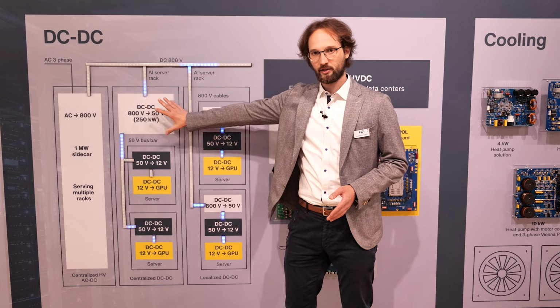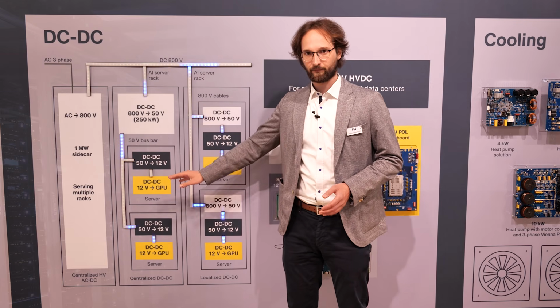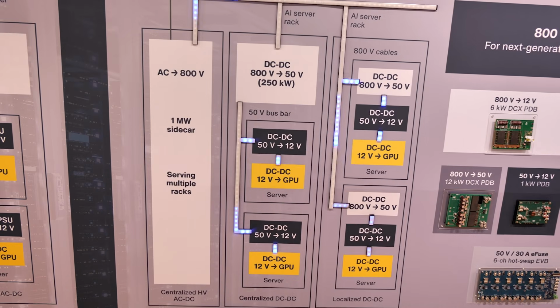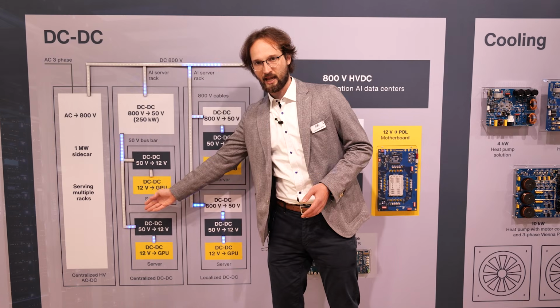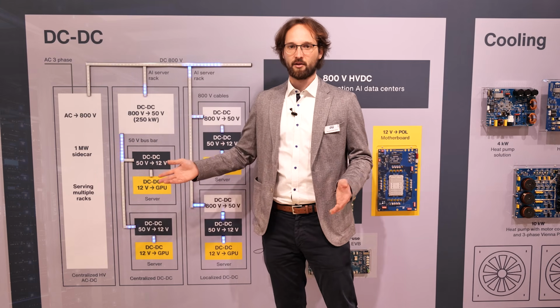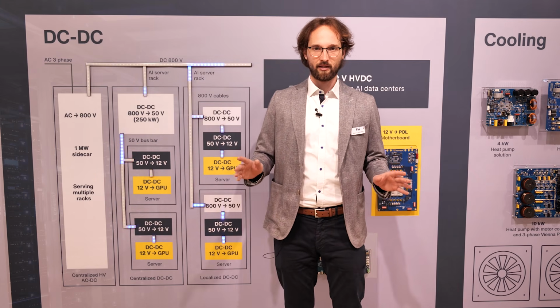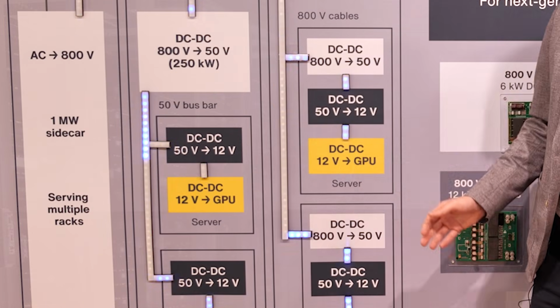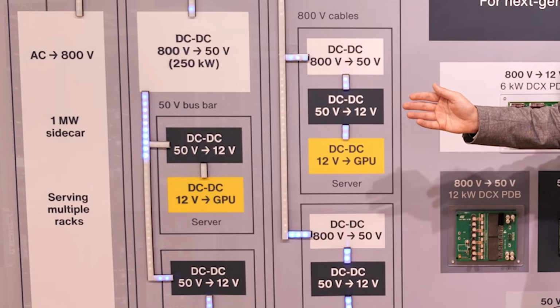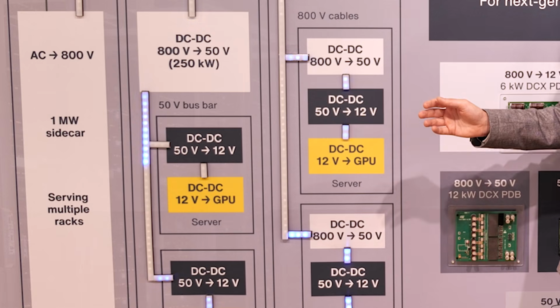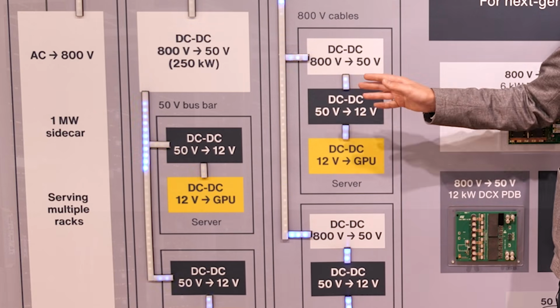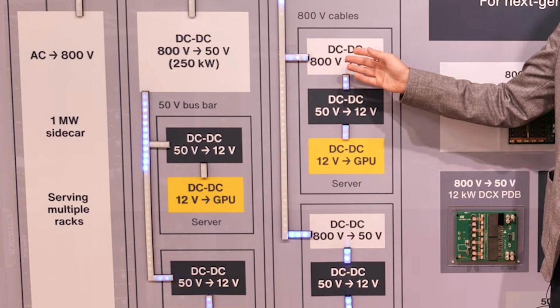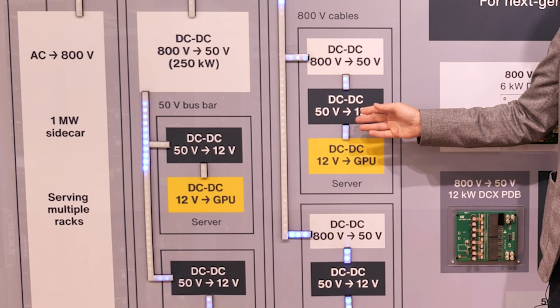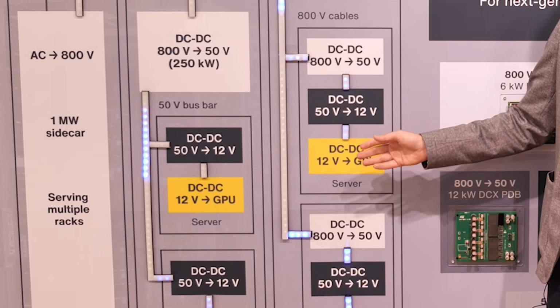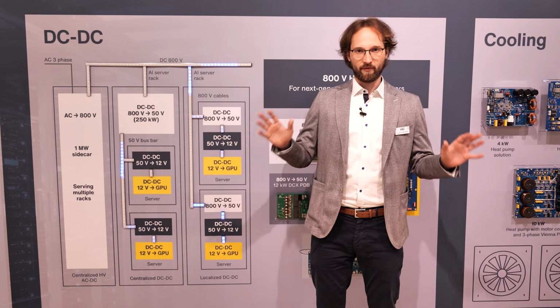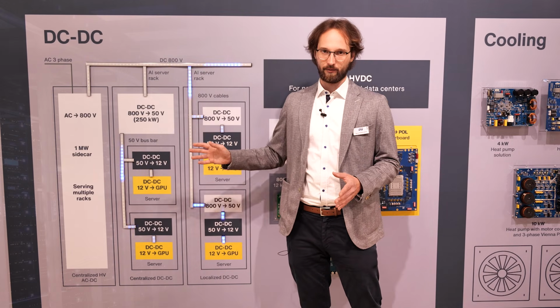The heavy lifting stage sits outside the server, while the existing rack interface stays familiar, the very same 50-volt bus bar as in the conventional solution, so no need to change the servers. The third is the localized DC-DC architecture. 800 volts run directly to each server, with 800 volt to 50 volt and 50 volt down to 12 volts happening per server. High conversion density per unit, fully modular.